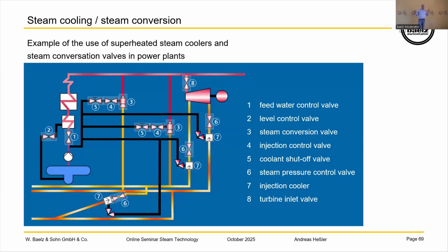Where is this needed? I made one example here, a power plant with a turbine. The red arrows show the hot, high pressure steam going through the turbine, which needs to be reduced in pressure and temperature. Then at the outlet we have lower pressure and lower temperature. At first we have our steam converting valve, where we reduce pressure and temperature. Then we have the injection coolers or control valves just for cooling down the temperature, because the pressure reduction in this case is made by the turbine.